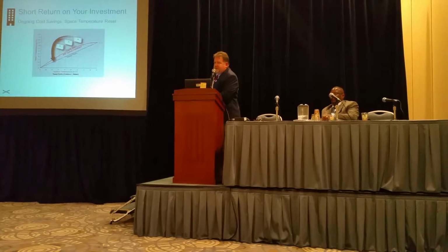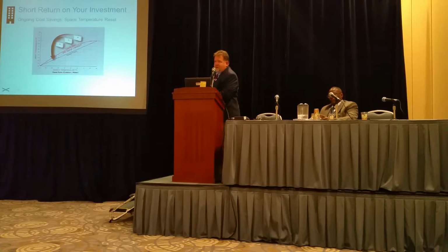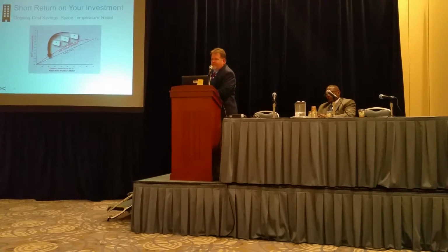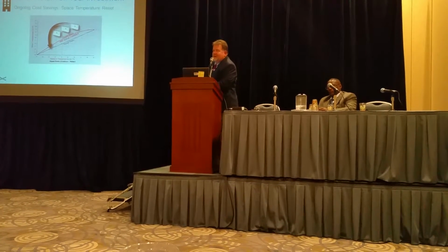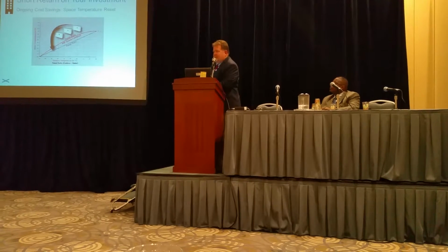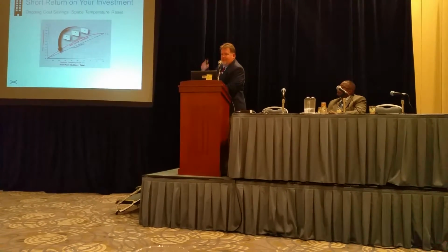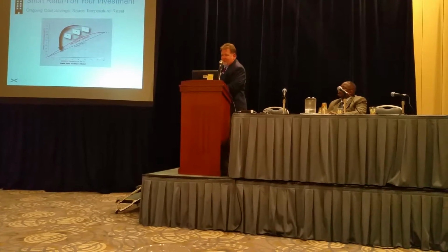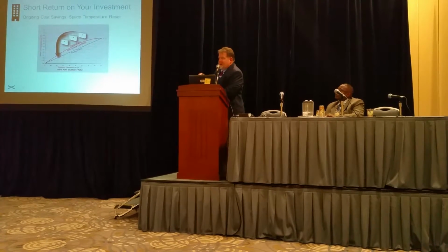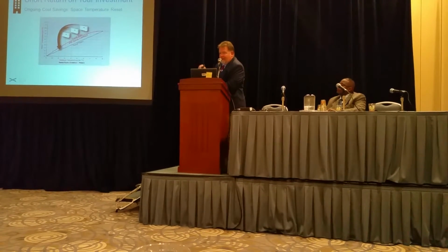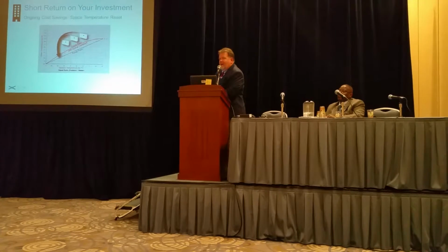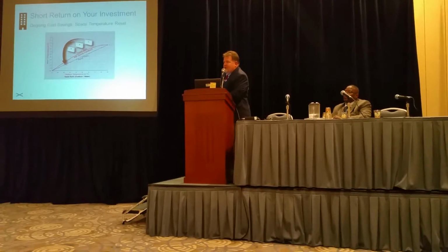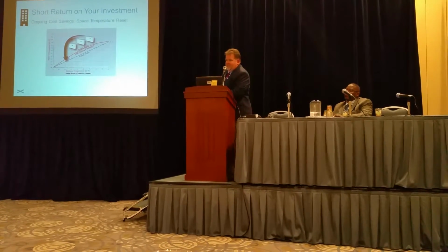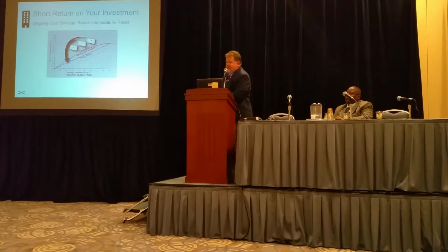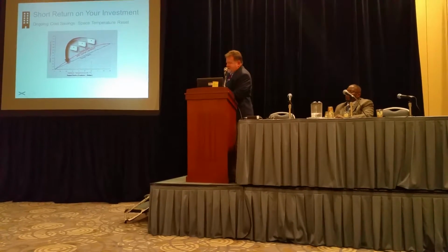A lot of technologies look simply at outdoor air temperature. Based on outdoor air temperature, this is what I'm going to do. But what I care about is, based on outdoor air temperature, based on predictive scheduling that comes in from the weather service as far as what kind of front is coming in, and based on what's actually happening inside the building, are we at set point or are we not? I want to make those decisions from there. So you can do a lot with a finely tuned automation system. To the end user, it's transparent.